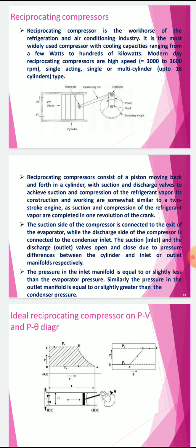The suction inlet and the discharge outlet valves open and close due to pressure differences between the cylinder and the inlet or outlet manifolds respectively. The pressure in the inlet manifold is equal to or slightly less than the evaporator pressure.